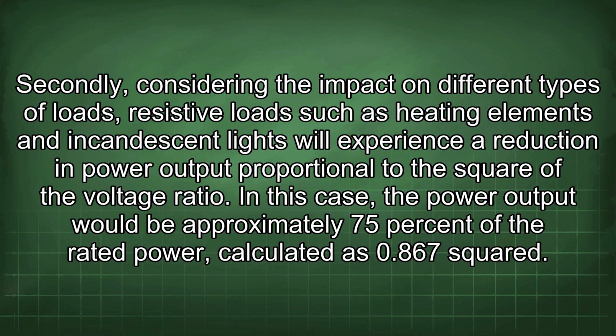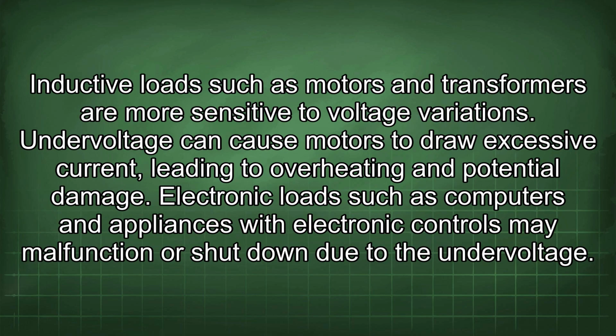Resistive loads such as heating elements and incandescent lights will experience a reduction in power output proportional to the square of the voltage ratio. In this case, the power output would be approximately 75% of the rated power, calculated as 0.867 squared. Inductive loads such as motors and transformers are more sensitive to voltage variations. Undervoltage can cause motors to draw excessive current, leading to overheating and potential damage. Electronic loads such as computers and appliances with electronic controls may malfunction or shut down due to the undervoltage.